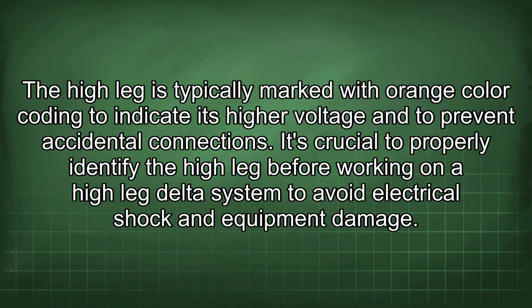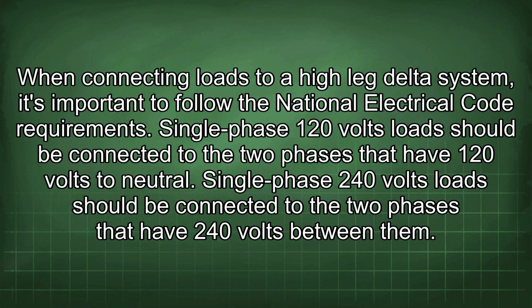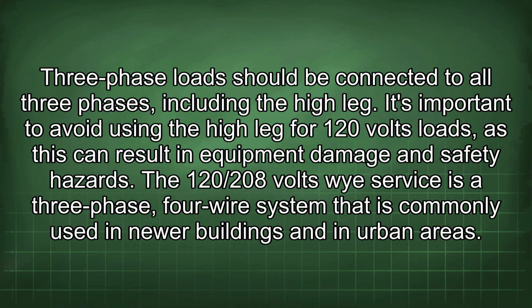The high leg is typically marked with orange color coding to indicate its higher voltage and to prevent accidental connections. It's crucial to properly identify the high leg before working on a high leg delta system to avoid electrical shock and equipment damage. When connecting loads to a high leg delta system, it's important to follow the National Electrical Code requirements. Single-phase 120 volts loads should be connected to the two phases that have 120 volts to neutral. Single-phase 240 volts loads should be connected to the two phases that have 240 volts between them. Three-phase loads should be connected to all three phases, including the high leg. It's important to avoid using the high leg for 120 volts loads, as this can result in equipment damage and safety hazards.